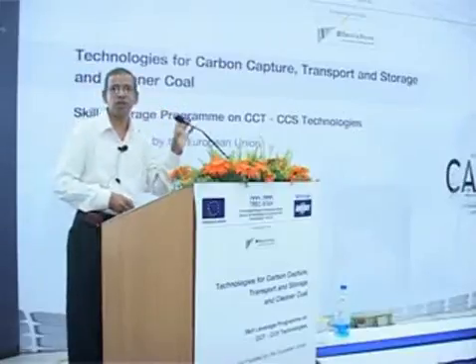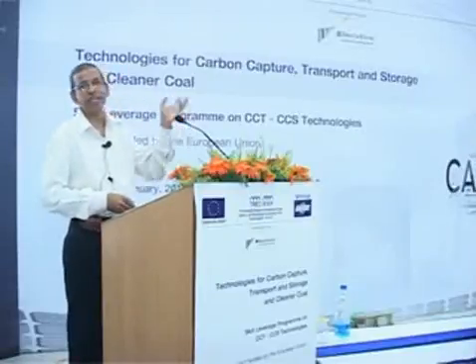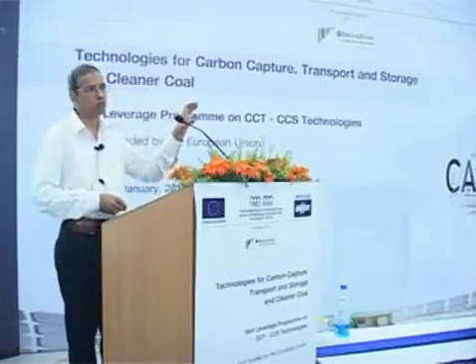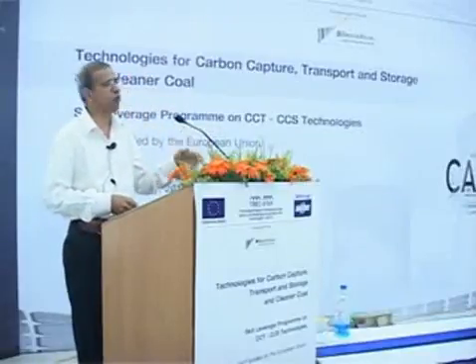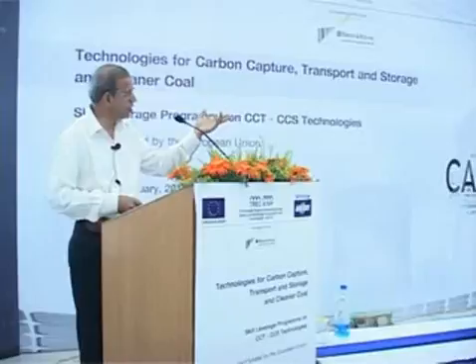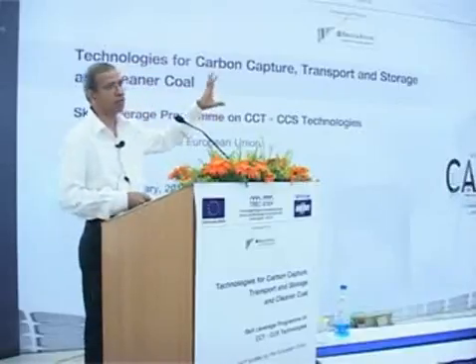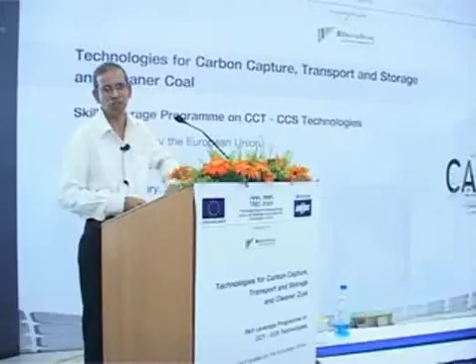Initially we started with only one system. Then we found the carbon content in ash was considerably high, with a maximum conversion of about 85% with one system. Then we thought, obviously it is not possible to go for 85% conversion and convince customers to buy this technology. So we went in for a fines recycling system to improve the efficiency. That was tested in this system. We established that fines recycling system here, similar to the loop seal in the CFBC boiler, which is being supplied by BHEL.